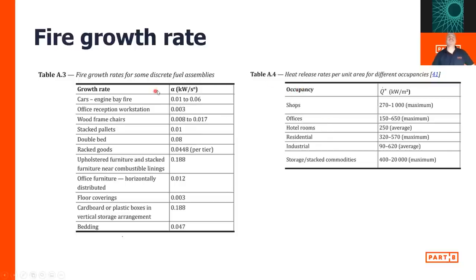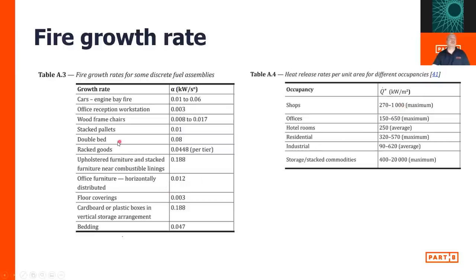Table A4 covers different fuel assemblies related to occupancies and gives you heat release rates per unit area — another way you can look at it. For a shop, that's 270 to 1000 kilowatts per square metre. You've got to look back and ask: what is the shop selling? If it's selling bedding, you're probably looking more towards 1000; if you're selling concrete gnomes, you're probably down towards 270. That's quite a useful set of tables, though you will not find those in BS9999 itself.